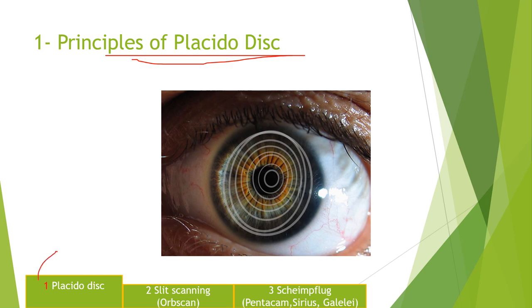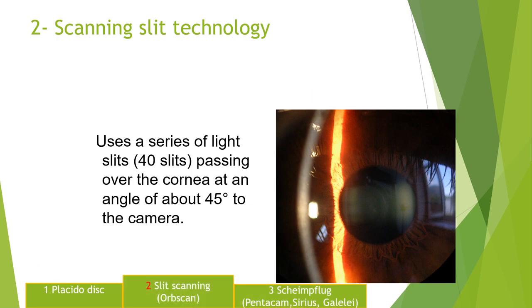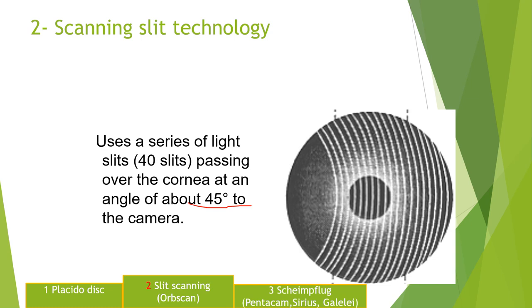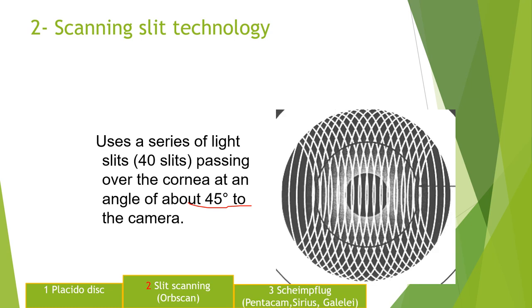Now we are going to the slit scanning. In slit scanning it's just like the slit on the slit lamp — you throw one slit and that gives you a thickness of the cornea. In the scanning slit technology, you throw 40 slits from the left hand side at an angle of 45 degrees, and then 40 slits from the right hand side, and the combined 80 slits give you the elevation data.